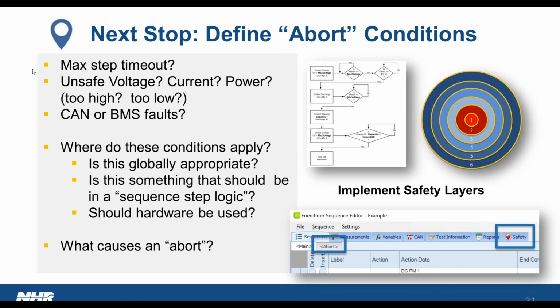Once I have this idea of what these are, when do these conditions apply? If they are global, applying anytime they happen, that's a layer 2 type of sequence safety and would go inside the safety tab. If something should stop just a specific step in the sequence logic, you'd add that into the flowchart, which is a layer 1, and you can optionally also add it into layer 2. For some conditions, you may want the hardware to actually trip or detect this and shut off—this can be done through programmable safety limits, which was the final warning, a layer 3, or through external means such as signaling for interlocks and e-stops in layer 4 or 5. But again, what we're asking ourselves is what would cause an abort, or a reason that we need to stop?